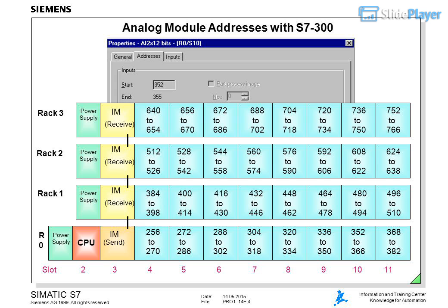You access the analog modules by means of load and transfer instructions. Example: the statement LP256 reads the first channel of the first module in rack 0. S7400. On the S7400, the address area for the analog modules starts at byte 512.